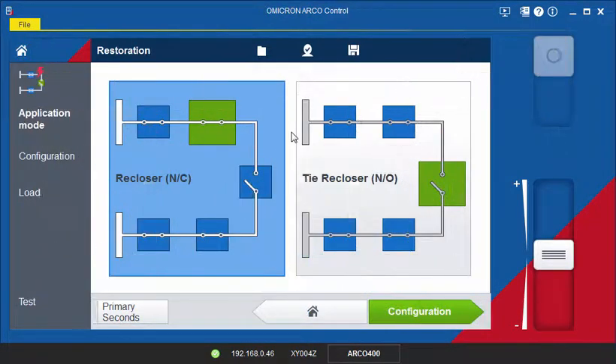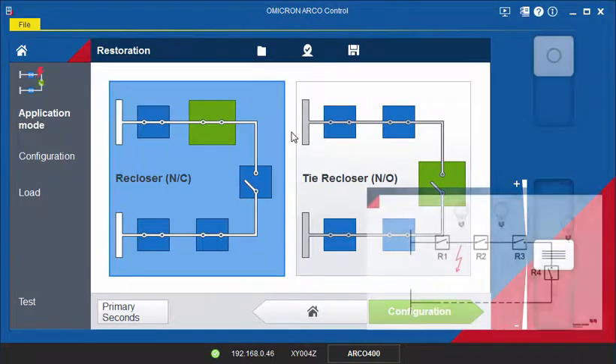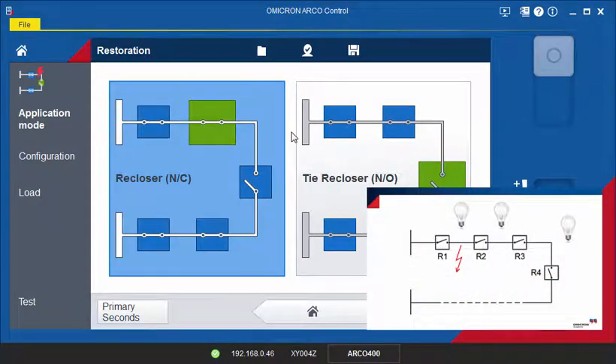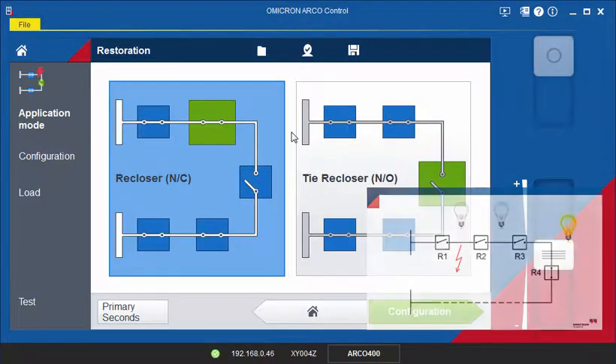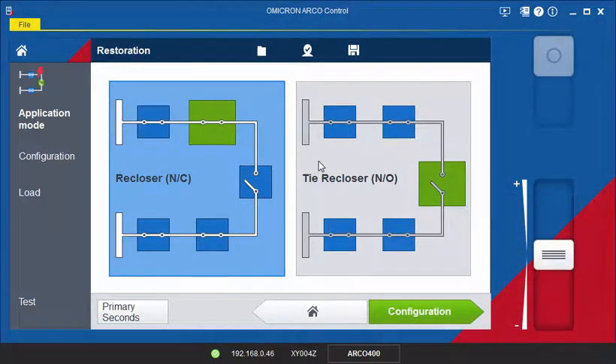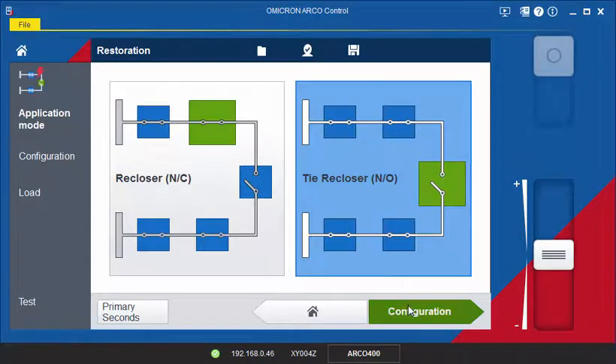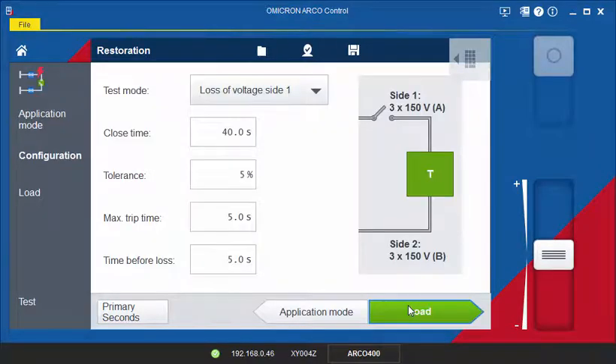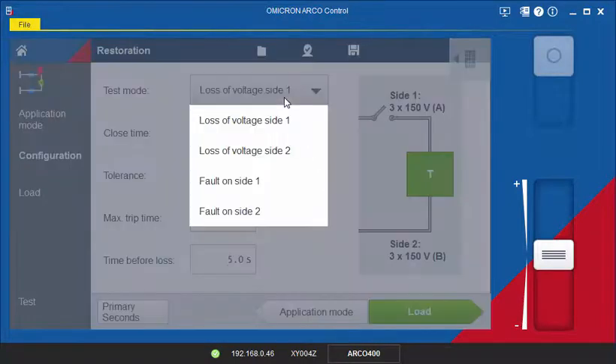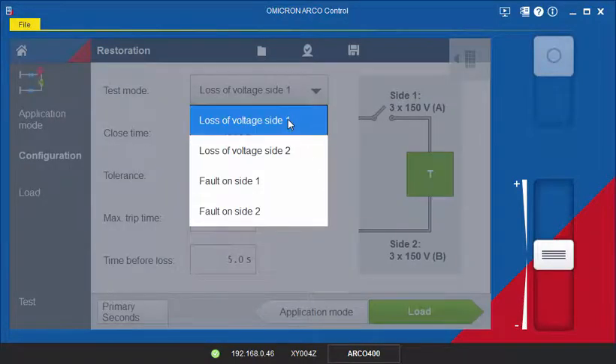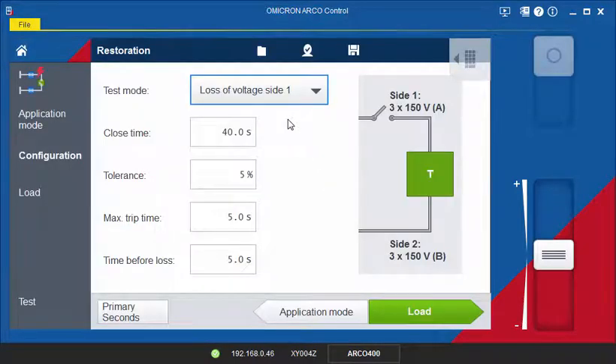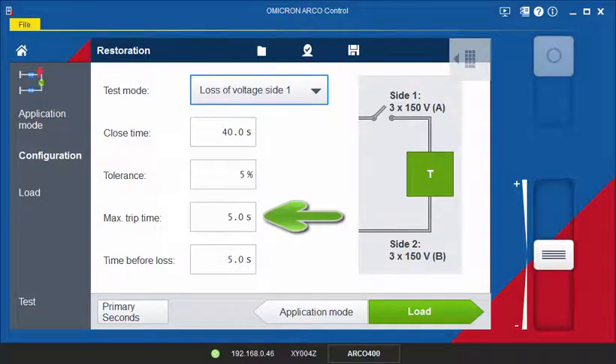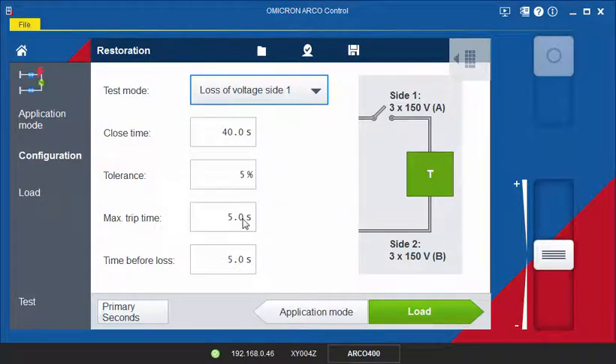Now, assume you are testing the tie recloser R4, which closes after it detects a loss of voltage on side 1 due to the opening of R2 and R3. Select the application Tie Re-Closer and on the Configuration page, select the test mode Loss of Voltage Side 1 from the drop-down menu. Enter the close time setting, the tolerance, and the maximum trip time for the controller.